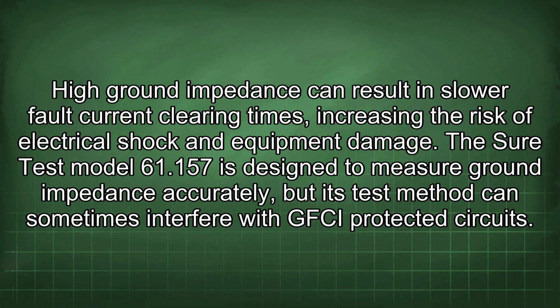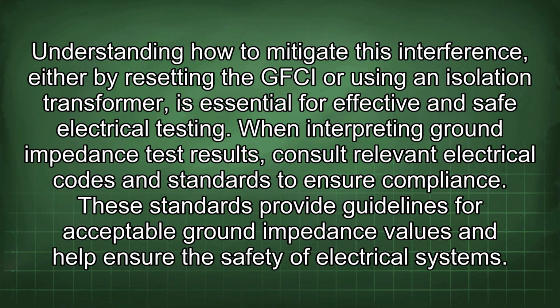61.157 is designed to measure ground impedance accurately, but its test method can sometimes interfere with GFCI protected circuits. Understanding how to mitigate this interference, either by resetting the GFCI or using an isolation transformer, is essential for effective and safe electrical testing. When interpreting ground impedance test results, consult relevant electrical codes and standards to ensure compliance. These standards provide guidelines for acceptable ground impedance values and help ensure the safety of electrical systems.